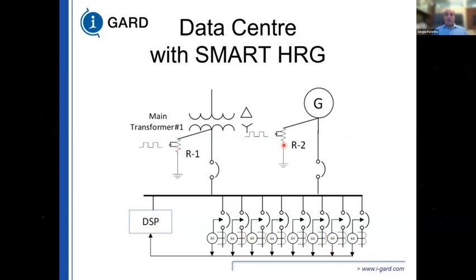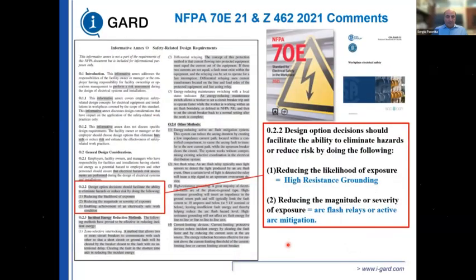The reason why I have only 2 resistors here is because the ground fault current is going to return back to the source. When you're here, it doesn't matter if the source is a transformer or if the source is the generator, the ground fault current will go back to the source. So we only have to have 2 resistors and 1 HRG system to protect your entire system. So reduce the likelihood of exposure, high resistance grounding, add an arc flash monitor relay, reduce the severity of exposure.